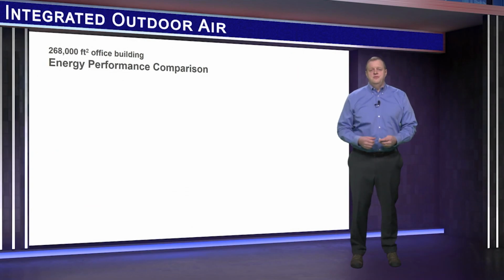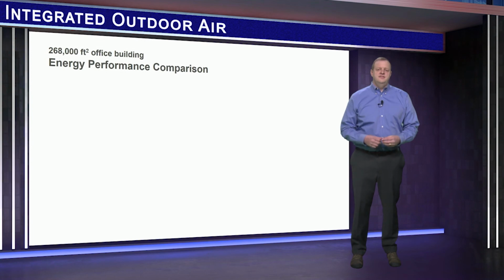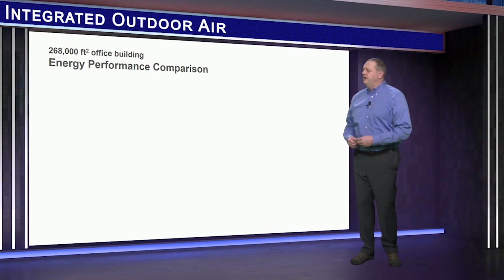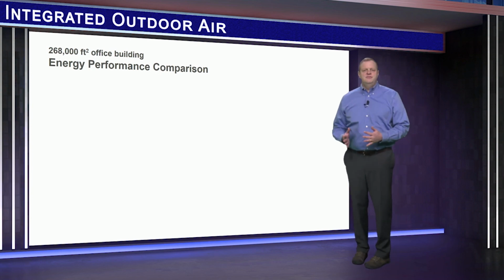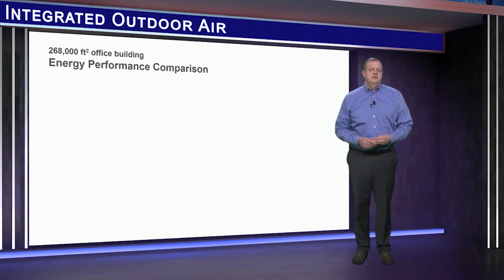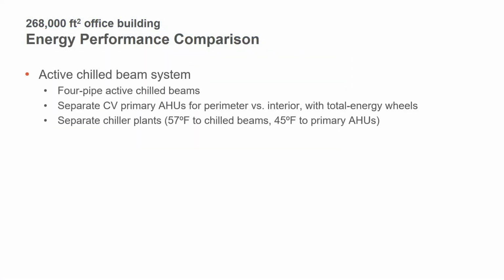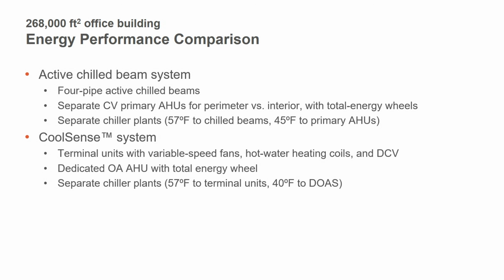To better understand the energy performance of this system, we used the whole building energy analysis software Trace 700 and modeled a mid-size office building. For our example, we compared the CoolSense system to an active chill beam system and a high-performance VAV system, and also to the ASHRAE 90.1 baseline VAV system. The chill beam system used 4-pipe active chill beams and separate constant volume primary air handlers for perimeter zones versus interior zones, each having a total energy wheel. The CoolSense system terminal units had variable speed fans, hot water heating coils, and demand control ventilation. The dedicated outdoor air handler also had a total energy wheel.